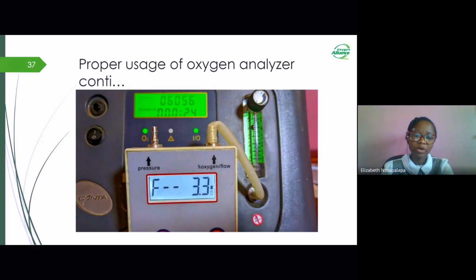Here the connection between the oxygen analyzer and the machine is secure, but there is some kinking happening. As we can see, the flow rate is showing 3.3, but we opened our machine to 5 liters. So these two demonstrations show that even as we're using the oxygen analyzers, if we're not doing it properly, if we're obstructing the hose of the outlet of the oxygen analyzer, or if there is any kind of kinking, we're definitely going to have different readings, which are not the desired outcomes for the oxygen purity produced by our machines. Next slide.